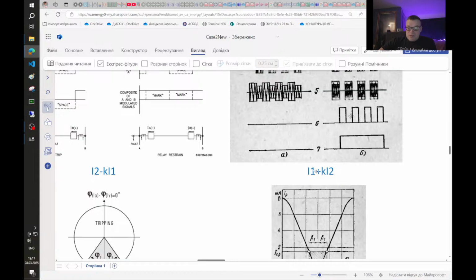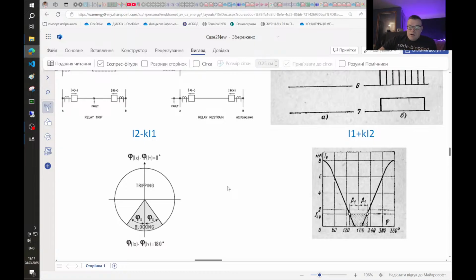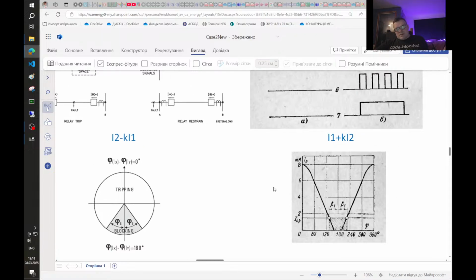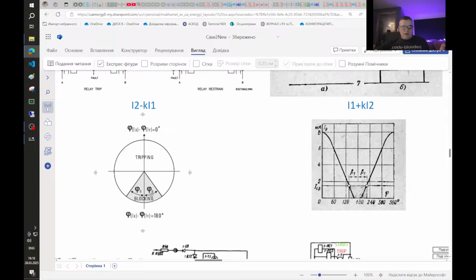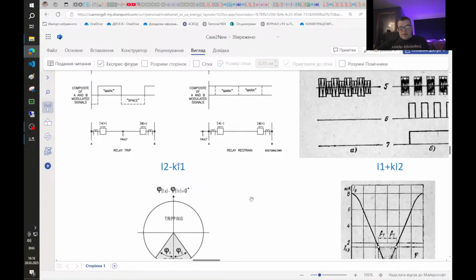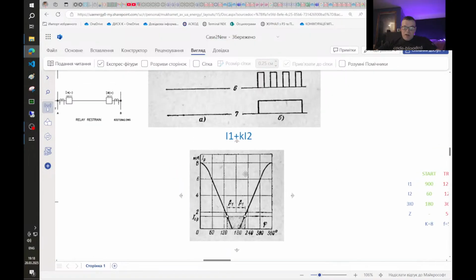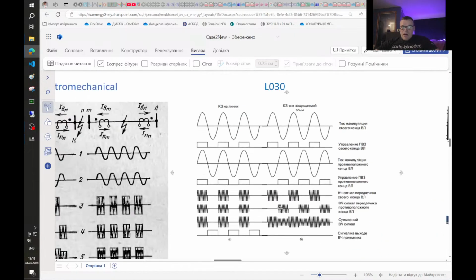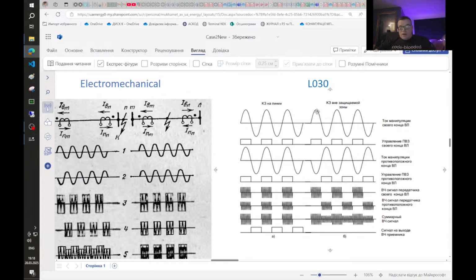If the pause is smaller than some angle, because we have the pause in the time domain, but this time can be equivalent to some electrical degrees. If the pause is smaller than a certain amount that is usually set in the protection, in that case the protection will be blocked. This is shown for the L60. This is for the old electromechanical relays, but the same is for the L30.